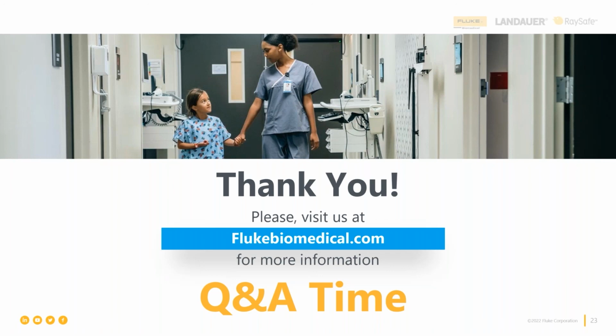Okay. And final question, how do I do the insulation resistance test with the ESA 612? How are the connections made? 612, 614, and 615. When we do the insulation test, this is the test with the Megohm button. It is a resistance test. And what we're looking for is the quality of the insulation around each of the conductors in our power cord and in our patient connections.